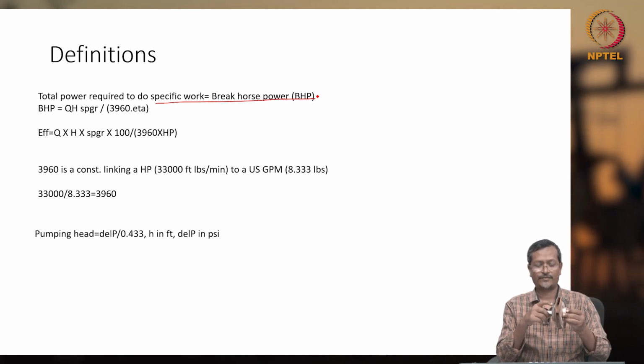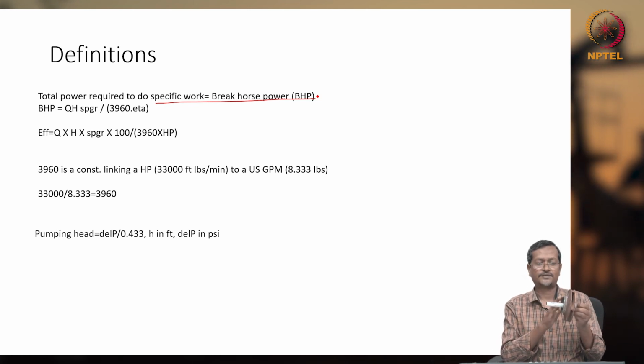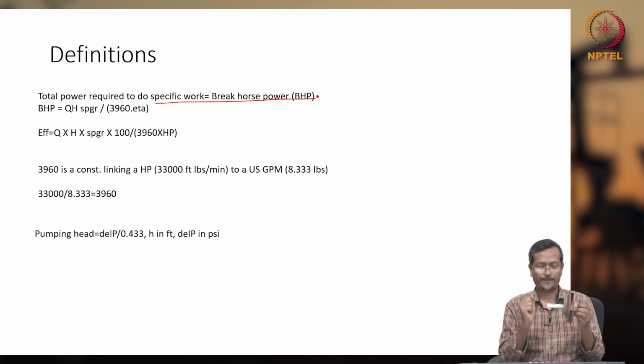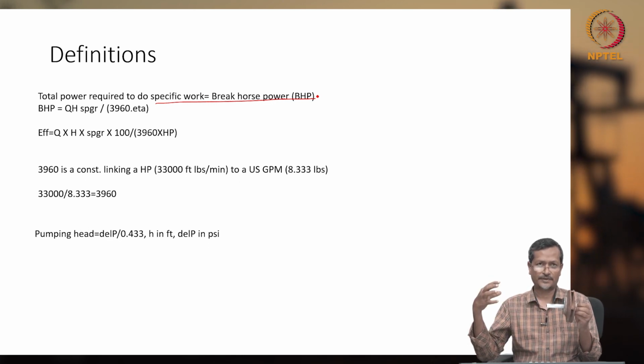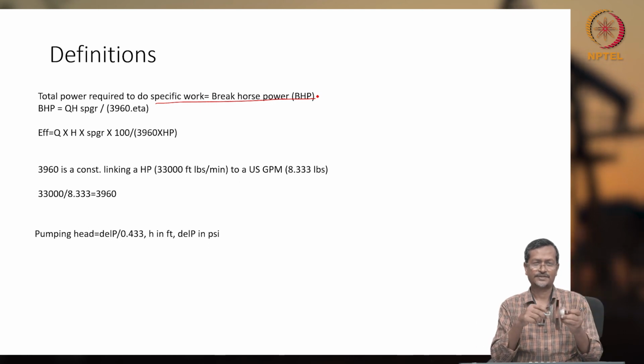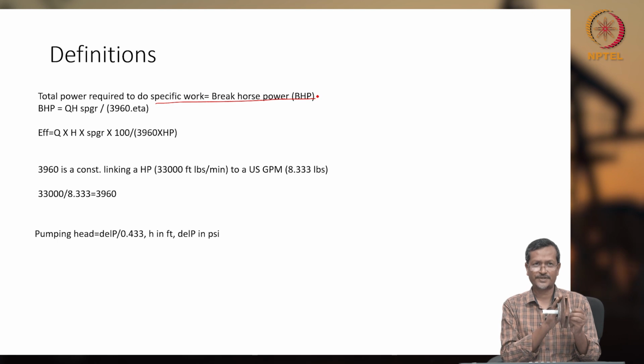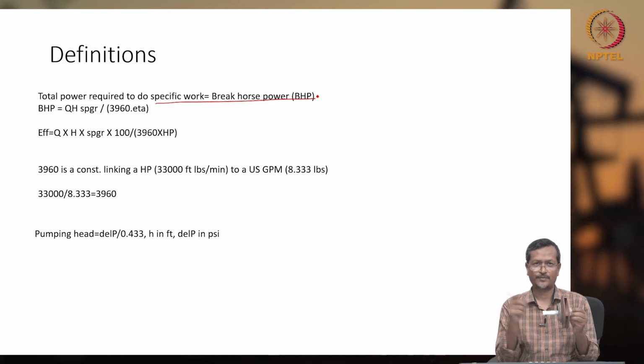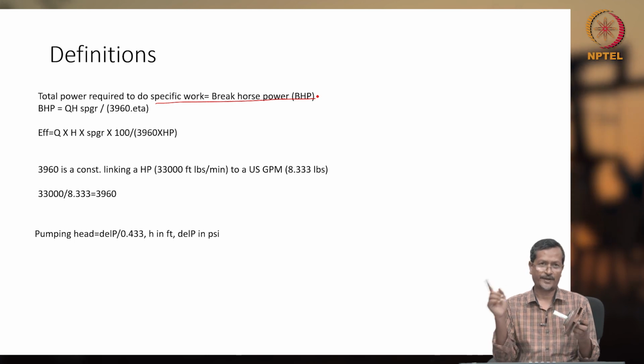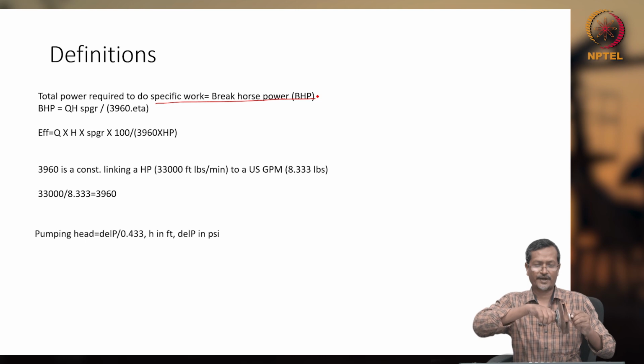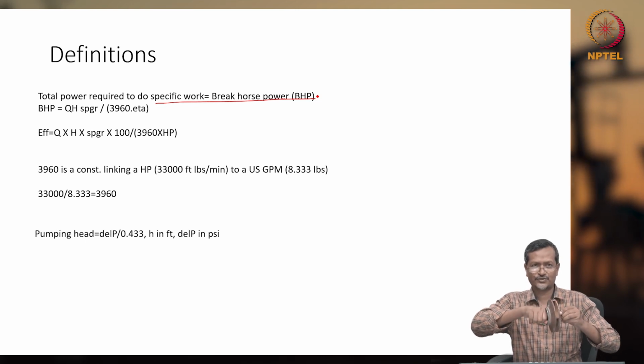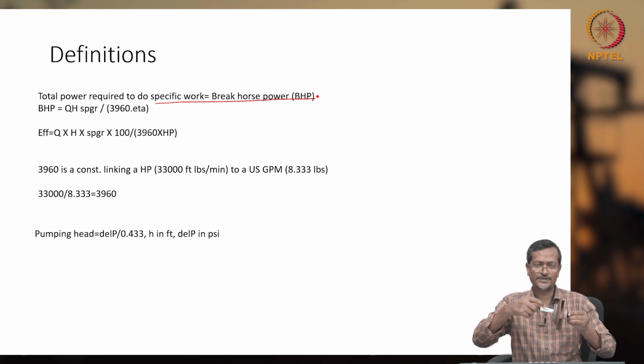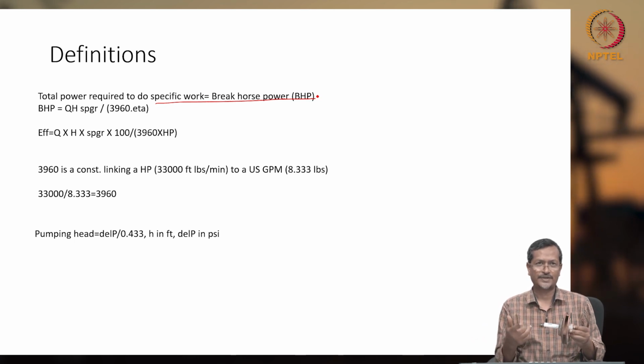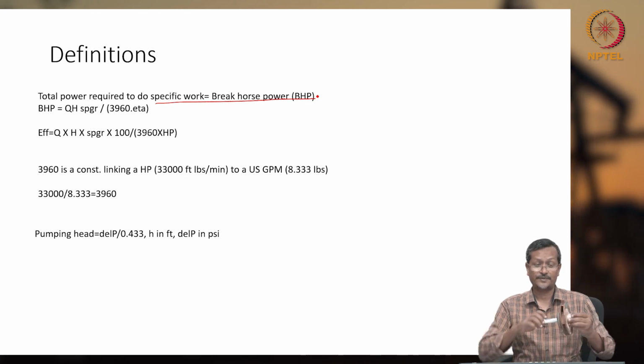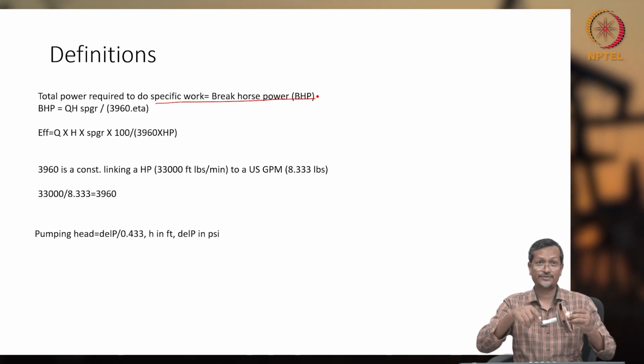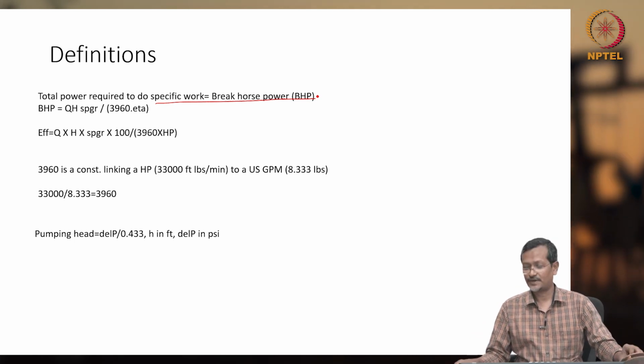There is a brake. So if the impeller can stop completely, that means it is using all the energy given by the motor, okay. But normally motor energy will be higher than whatever it is consuming, so the system will be running continuously. If this energy consumption is higher than the motor, then the motor will not be able to deliver, so then the motor can fail actually, okay. So in that case, motor power will be higher than your consumption energy. And if you are using some dynamometer and you are forcing it to stop, so that much it is consuming some energy. So that way the dynamometer people will be measuring brake horsepower, okay. It is as if you are applying a brake, and how much energy you are consuming when you are applying the brake, okay. That is called brake horsepower.